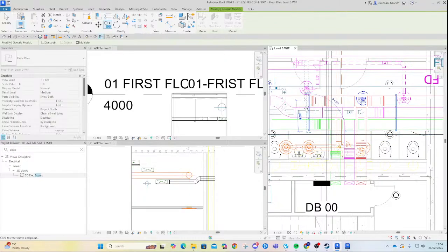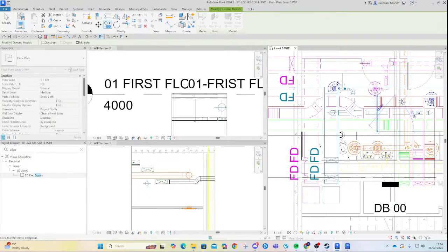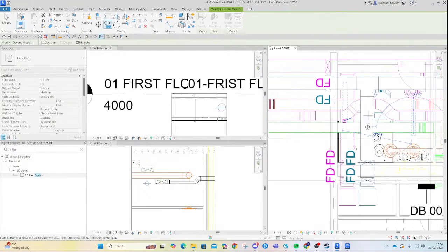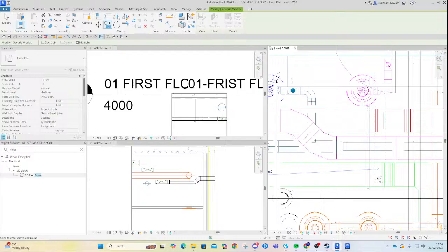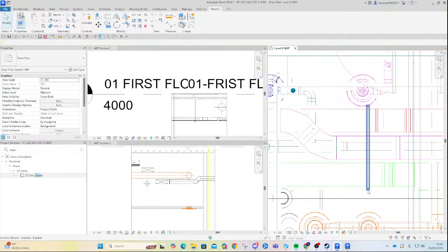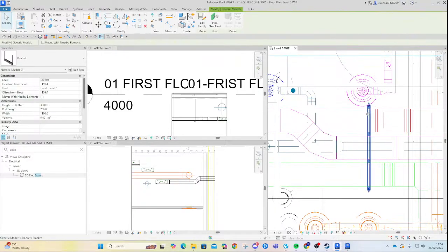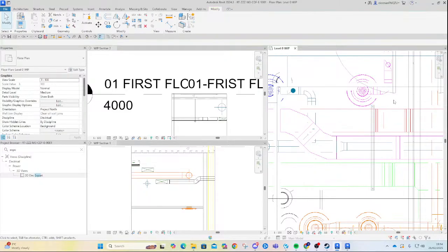Just to be on the other side of all those bends, because we know that this drops down, then levels off, then it changes again. It's a bit awkward. So what actually will happen on site or in the field, in those areas, is something bespoke will be created for those brackets. So like this one here, we can see is going to clash, so we're going to have to tab that one back a bit.